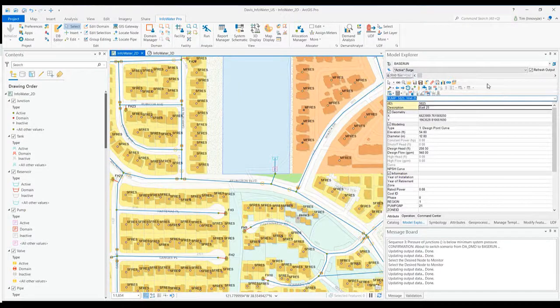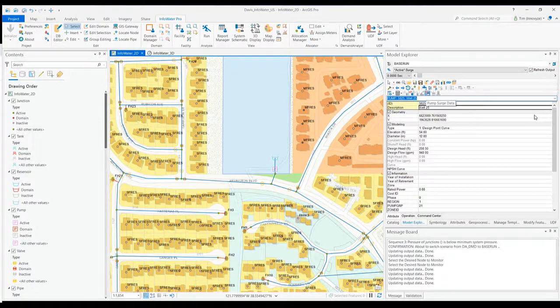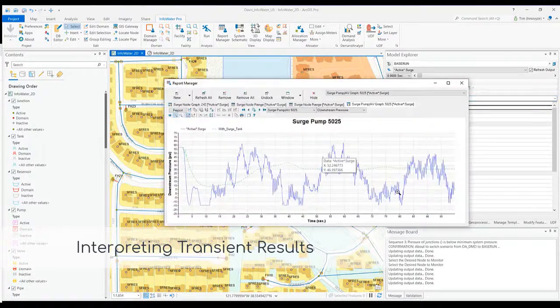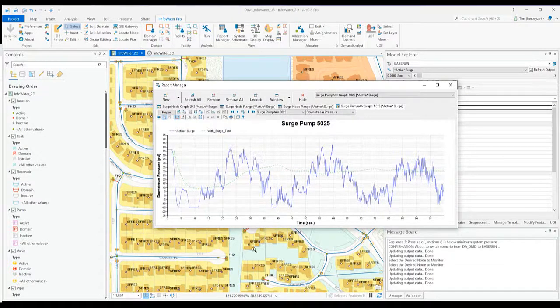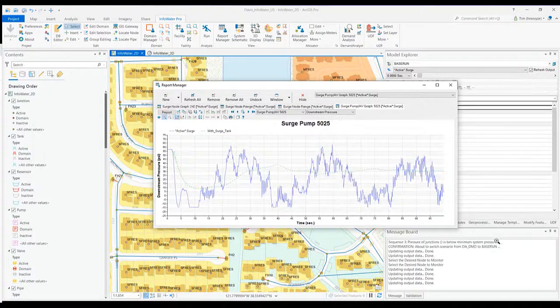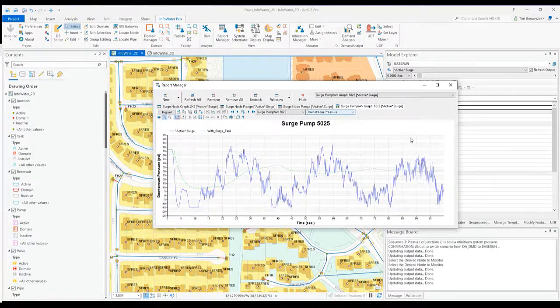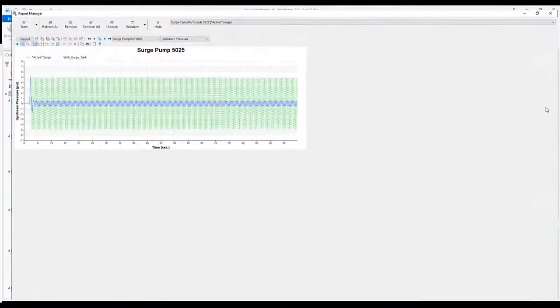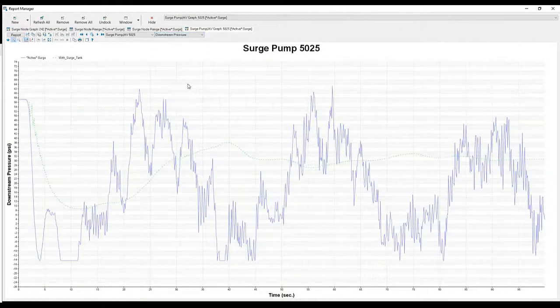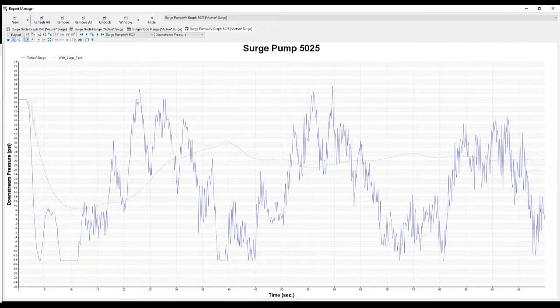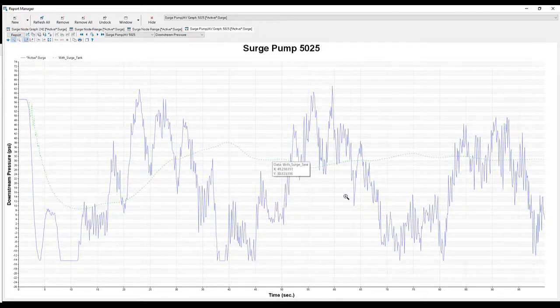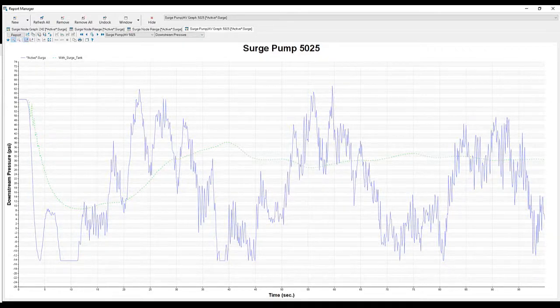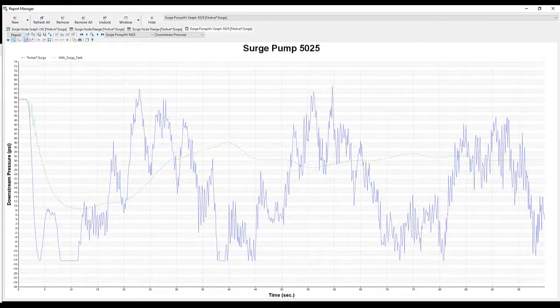Once you have that event, you run your surge analysis. Then you can come in and look at this report. Here you can see this purple line is the surge event. You can see the surge, the fluctuations on the downstream pressure for this pump. Downstream pressure is where you're really seeing that transient event without the surge protection. Then I've run this with the surge tank as well, that's this green line where you're seeing that event be mitigated a little bit.